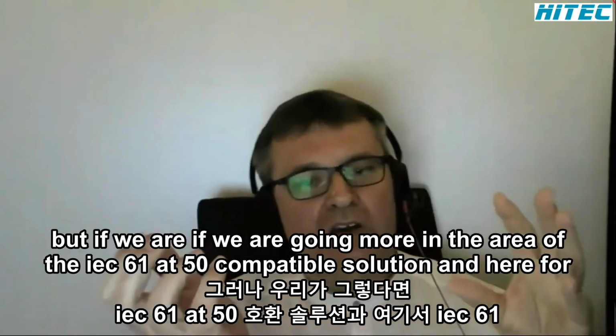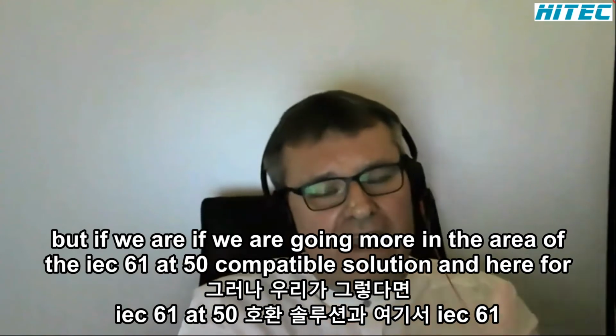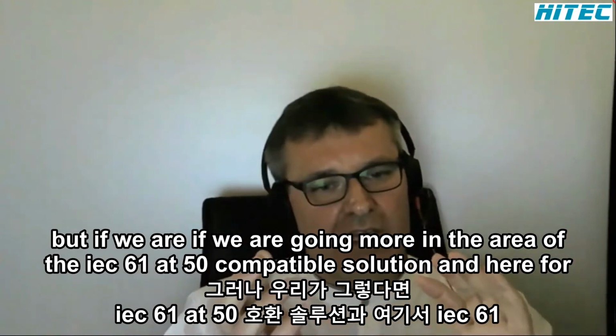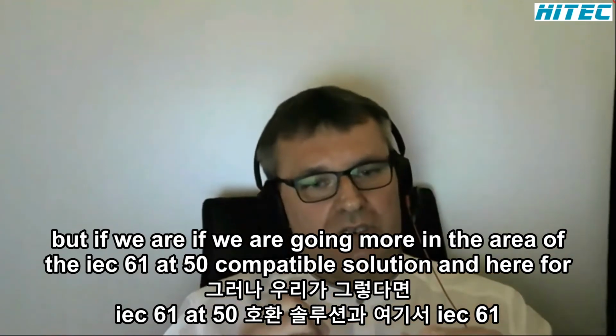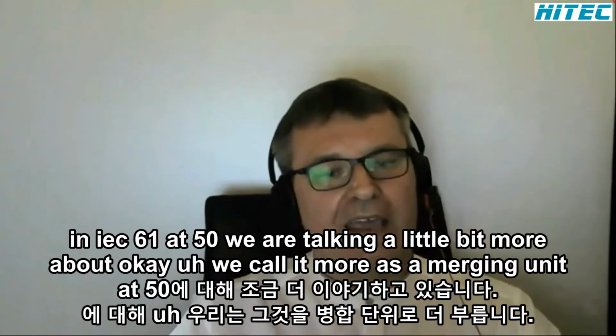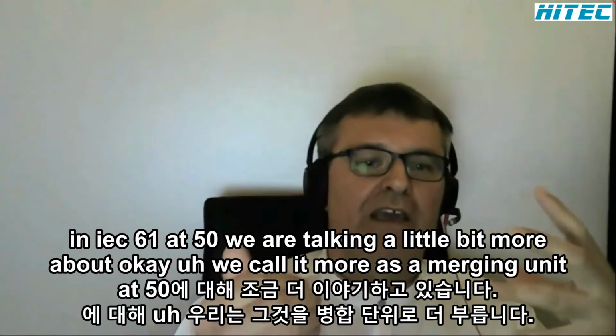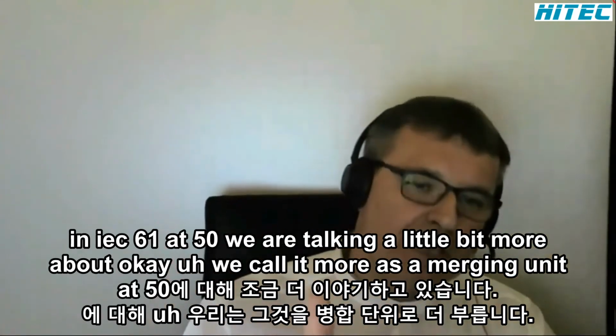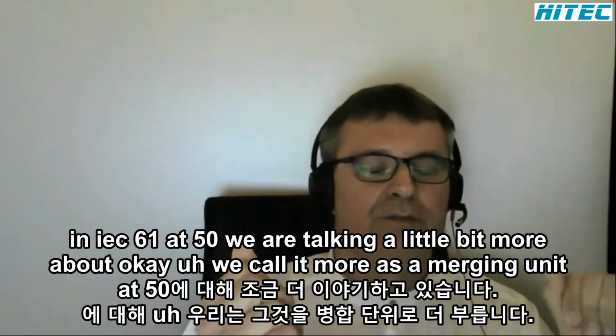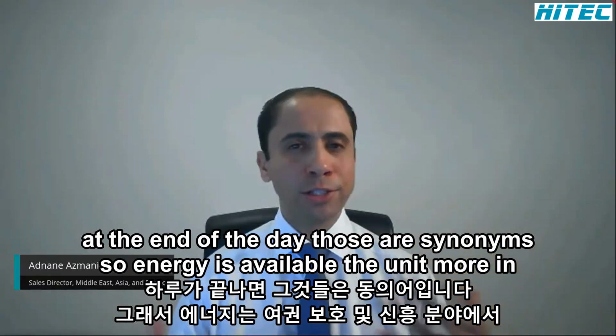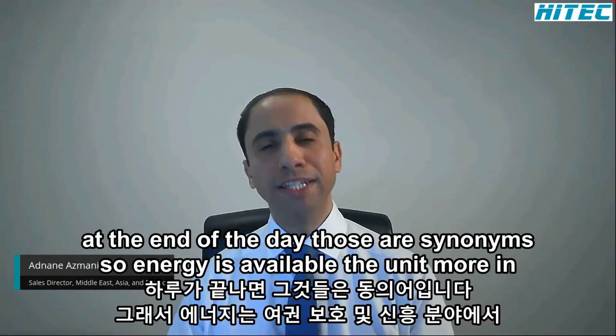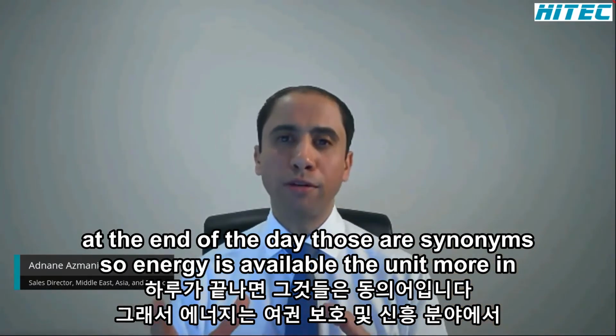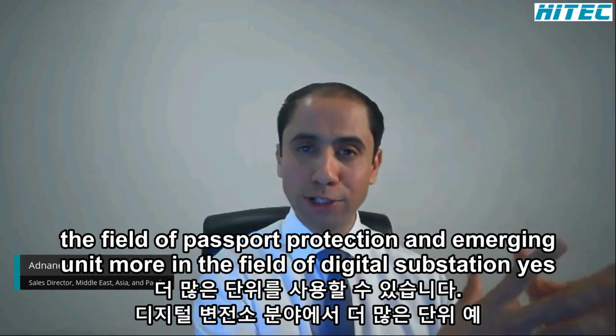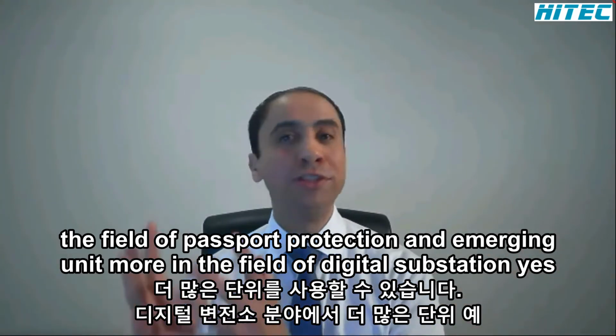But if we are going more into the area of the IEC 61850 compatible solution, in IEC 61850 we are talking a little bit more about, okay, we call it more the merging unit. At the end of the day, those are synonyms. So a merging unit is a bay unit. Bay unit more in the field of busbar protection, and merging unit more in the field of digital substation.